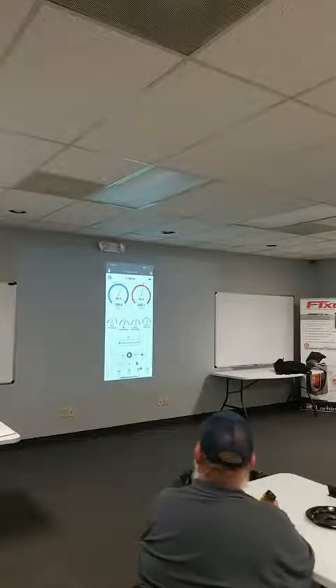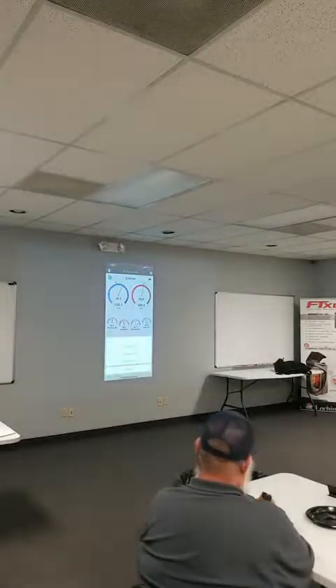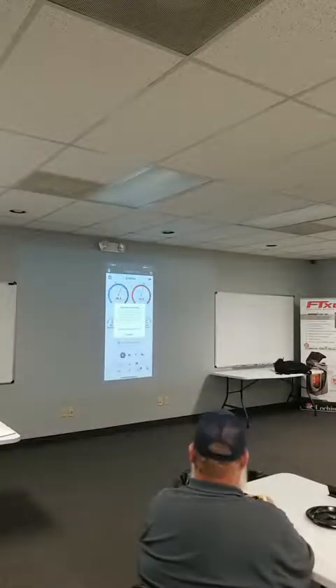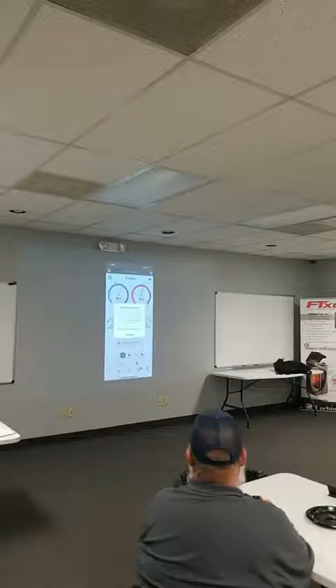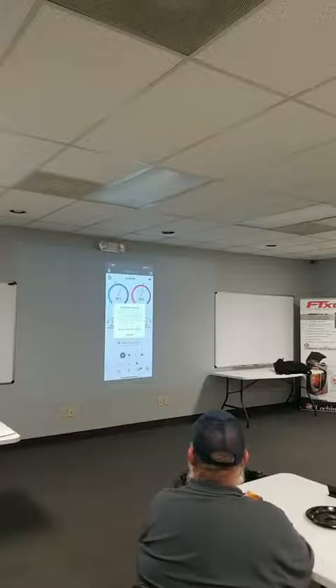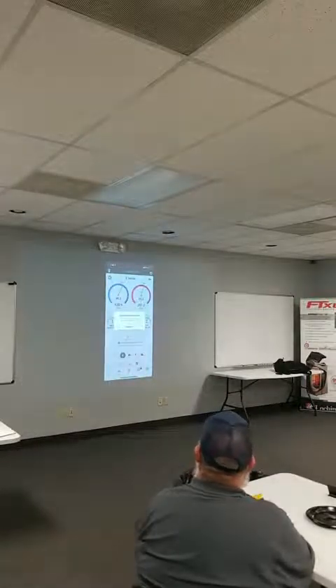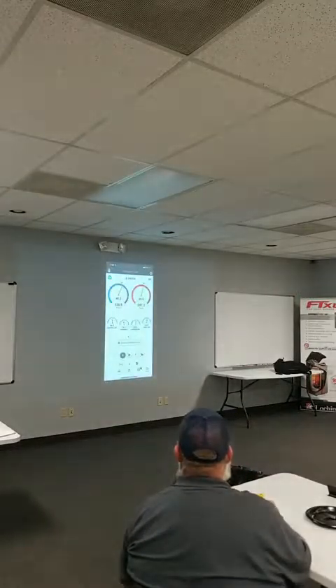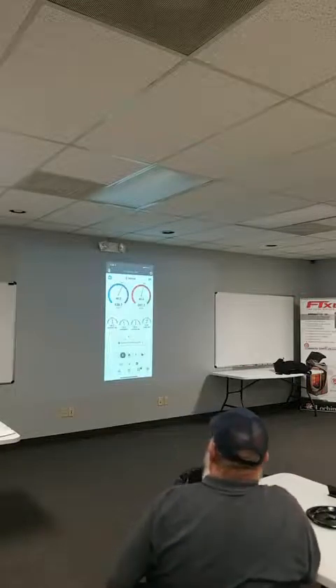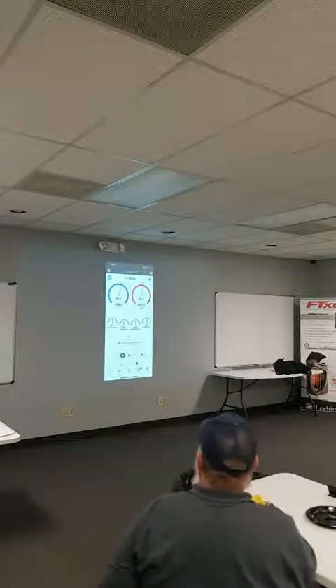Now, let's say this is the way the system is supposed to be. If we set a benchmark here, it's going to tell us we're benchmarking under duress, saying, hey, you idiot, the charge is out of range, but maybe the customer won't fix it. So it's like, I told them it's this, but I have to benchmark it so we know this is the way I left it. So I'm going to benchmark this under duress. It's going to tighten those targets up and line them up with the 20 degrees of subcooling and the problems.